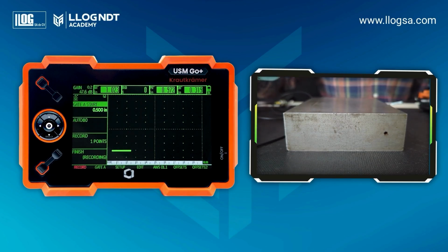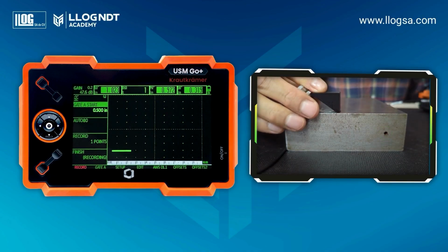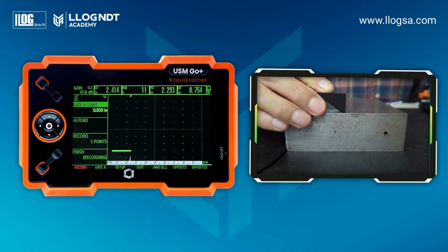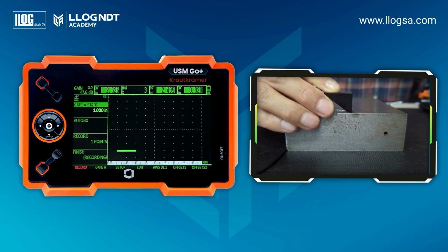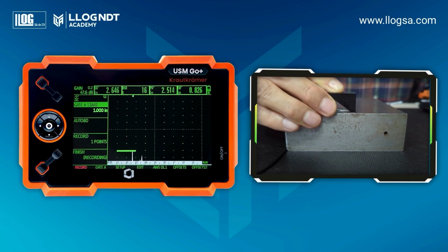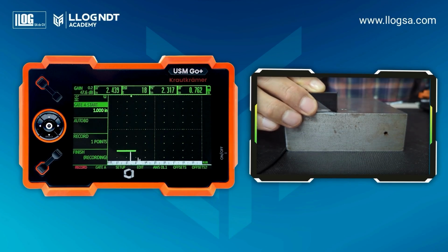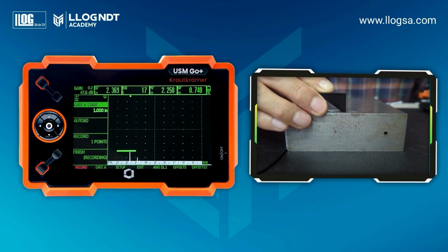Now, place the transducer directed toward the hole located at 1/2 T. Position the gate over the echo and move the transducer back and forth until finding the maximum echo amplitude. Without changing the gain, go to the record function and press the right key to save the second point.